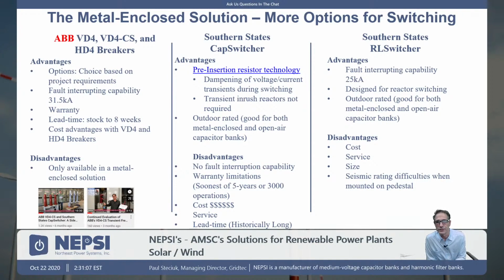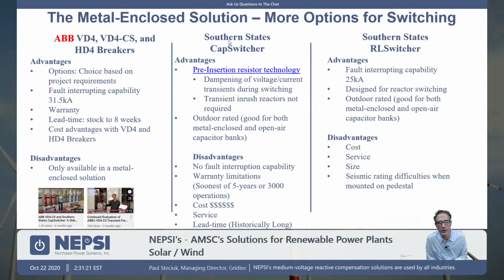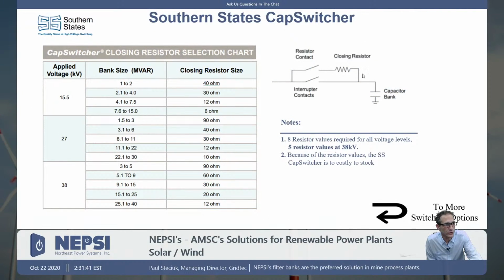So let's just talk about your switching options. Remember, if you're open air, you're going to be pushed into this category here because the Southern States cap switcher is an outdoor rated device. Open air meaning everything's exposed to the environment, and you're forced into that technology. You're forced into their lead time, and one thing about the Southern States cap switcher you have to realize is you do want to plan ahead because there is pre-insertion resistor technology here. The rating of this resistor is based upon the table, and you have to wait until the study is completed to choose the resistor, and then you have the proper switch.